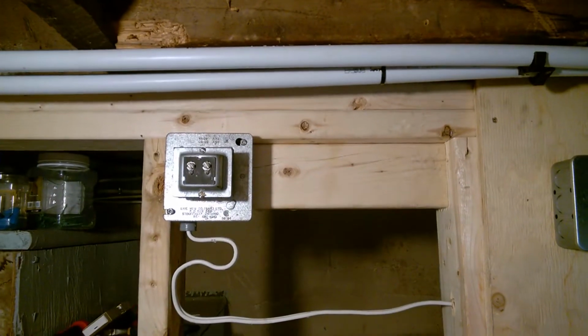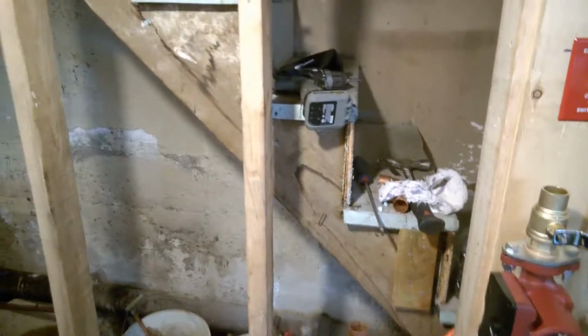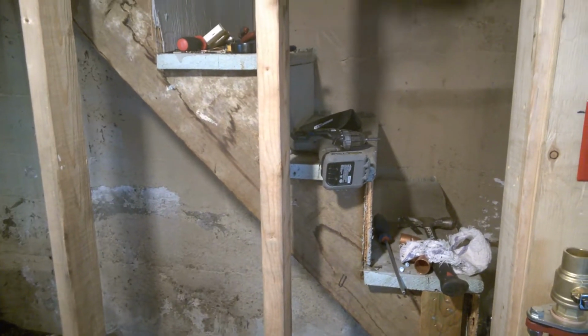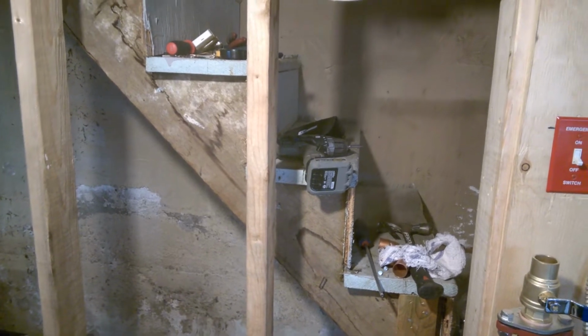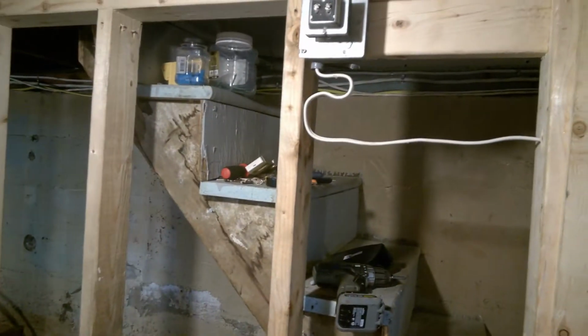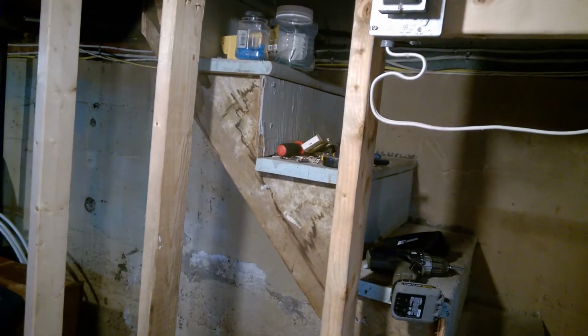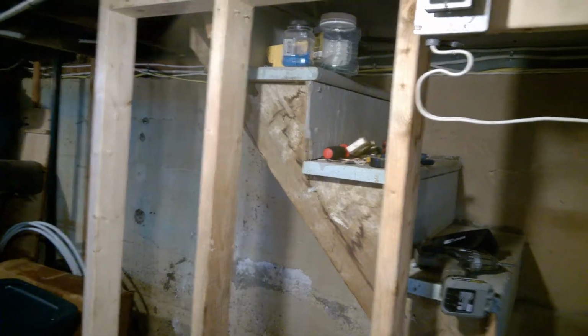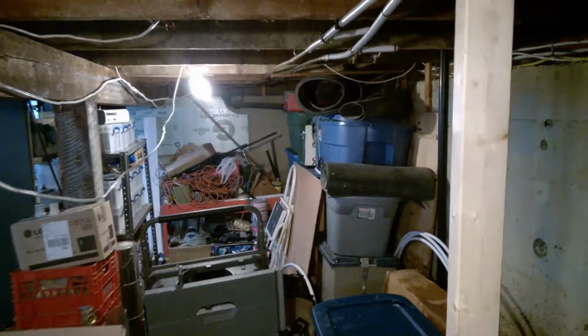transformers, because you're only allowed 4 zones per transformer. So I'm gonna need another 2 of those, and I think zone valves are $80 or something a piece, or $90. And then valves are like $15 a piece, shutoff valves, and you need like 30 of them, because you need 2 per zone valve, and then 1 on the return. And by the time you get the elbows in, the adapters, blah blah blah, I should have got them to do it. And that doesn't even include all the piping.